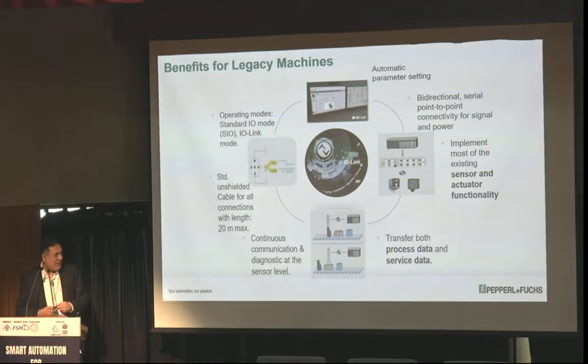Secondly, another thing which we can extract is we get both process and service data, right? So whatever is the process value is going in for the controlling purpose, but service data is also available, which allows you to do a lot of diagnostics of it. Simpler example, you have used an inductive sensor, right? An inductive sensor is supposed to sense the presence of a metal target. Now, due to vibration on the machine, the screw gets loosened. As a result of that, the position of the inductive sensor shifts.